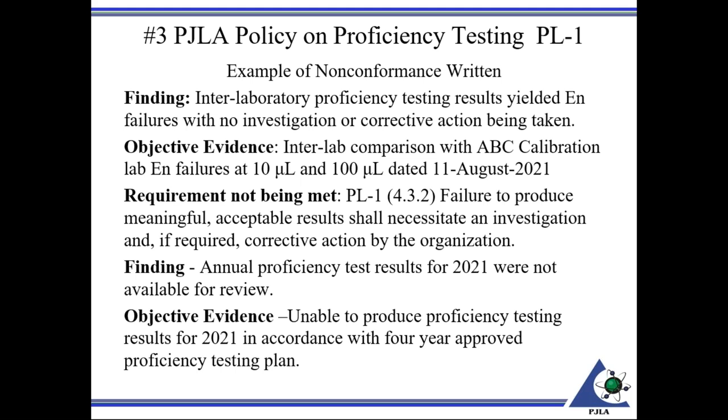So here's an example of non-conformances written in regards to PL1. Interlab proficiency testing yielded EN failures with no investigation or corrective action. Interlab comparison of ABC lab with ABC calibration lab, EN failures at 10 microliters and 100 microliters. It was probably a pipette. Dated 11 August 2021. So this particular instance, yes, they probably did the proficiency test. They established predefined limits.